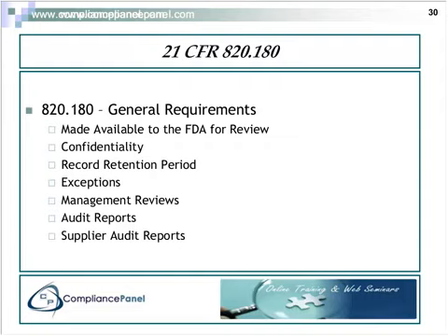If anything is confidential, as the FDA comes through your facility and performs their investigation or audit, and they ask for copies of certain records that you feel are confidential, then you need to stamp them confidential, because any and all information gathered by the FDA becomes part of public record under the Freedom of Information Act.